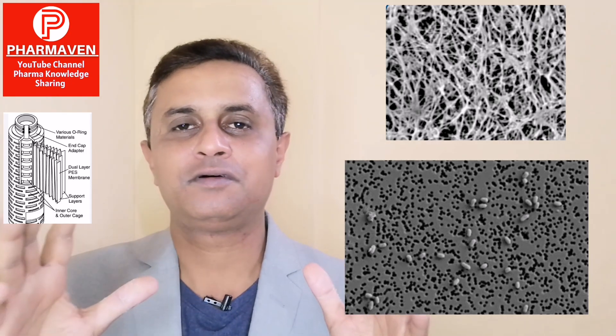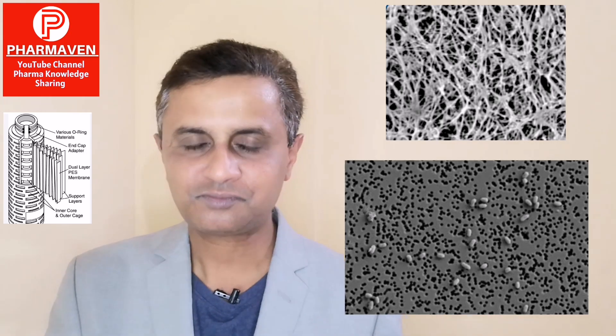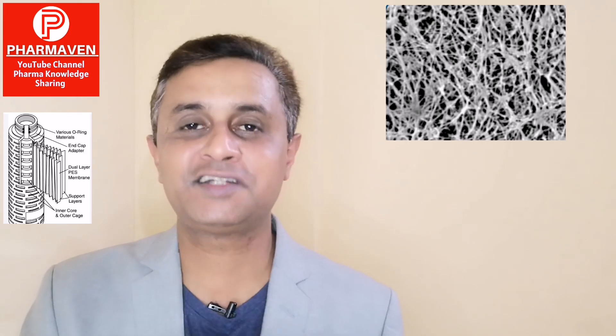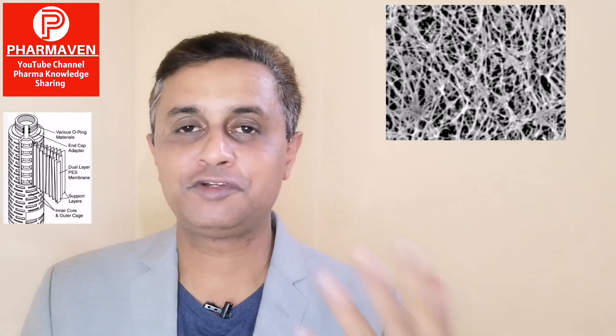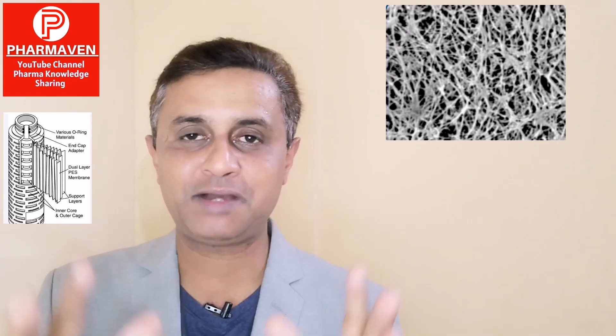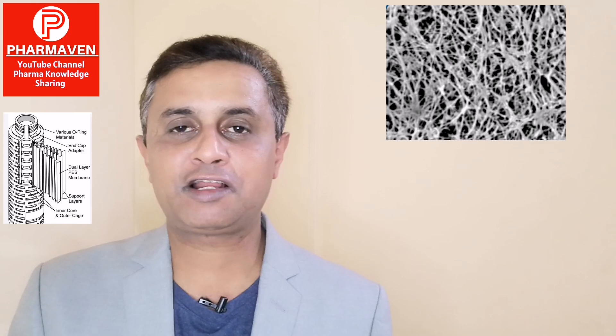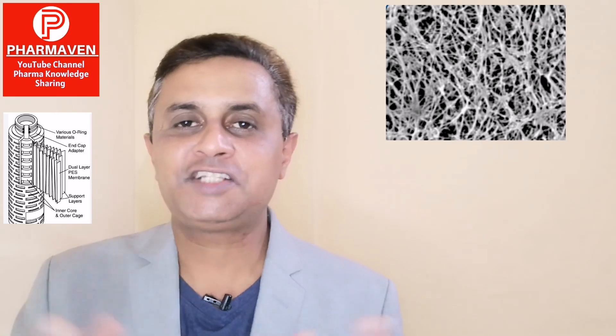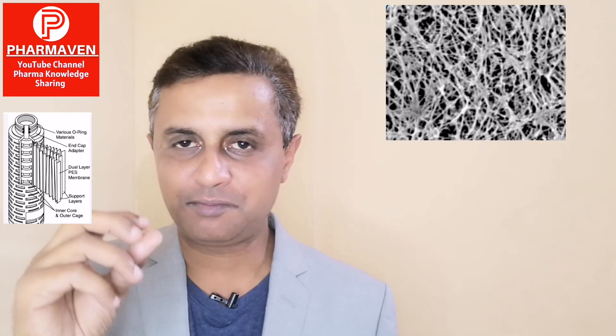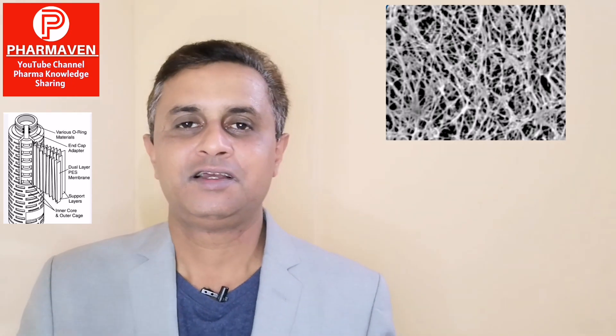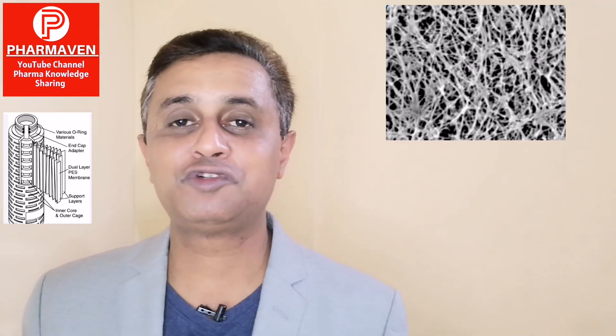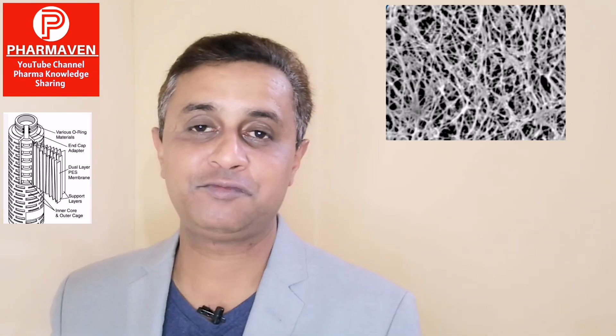The second mechanism is adsorption, which is charge-related. It is impacted by the composition of the liquid, temperature, and filtration conditions. By adsorption, microorganisms adhere to the microfibers of the filter. Through this mechanism, even if the bacteria size is smaller than the pore size, if the adsorption sites are available on the filter structure, they will be retained. So by adsorption, even bacteria smaller than the pore size of the filter will get retained.